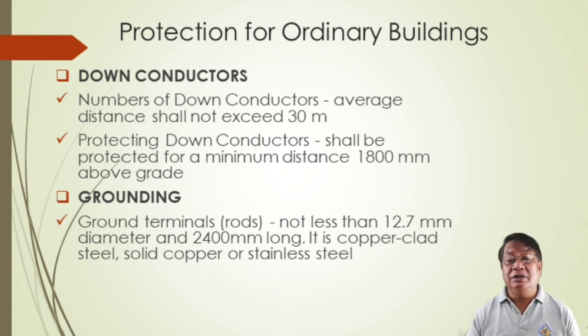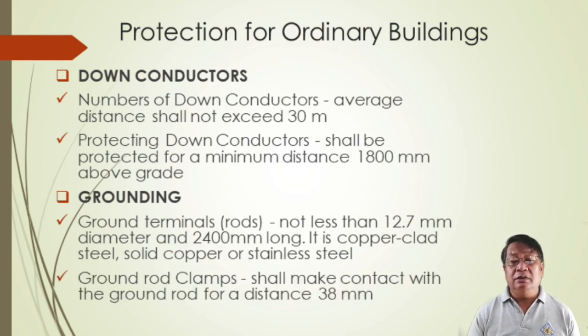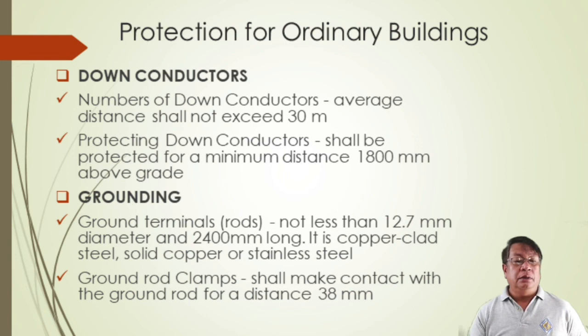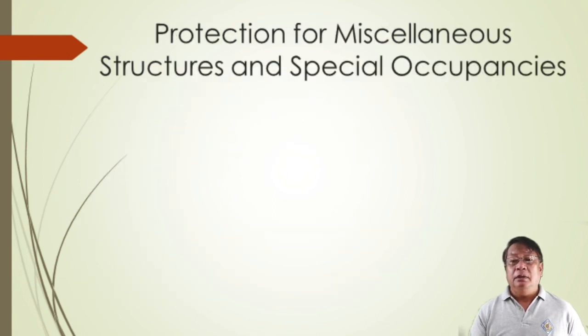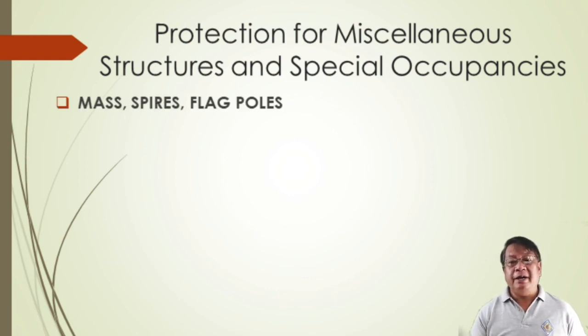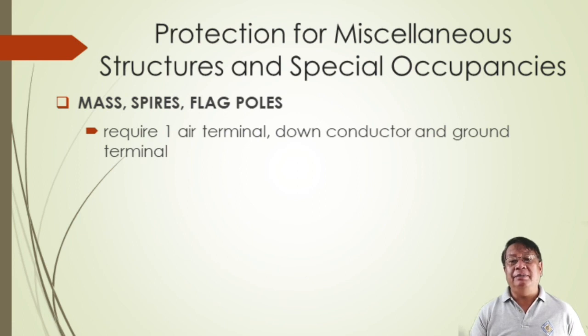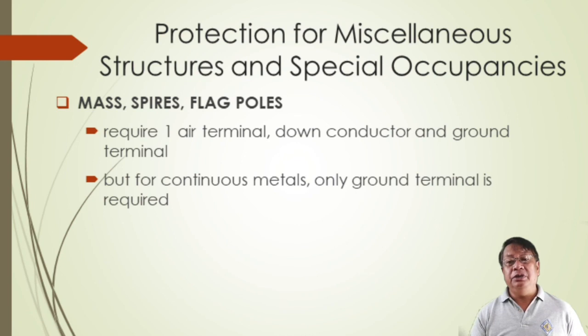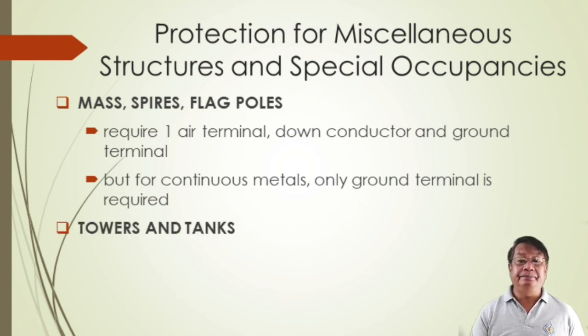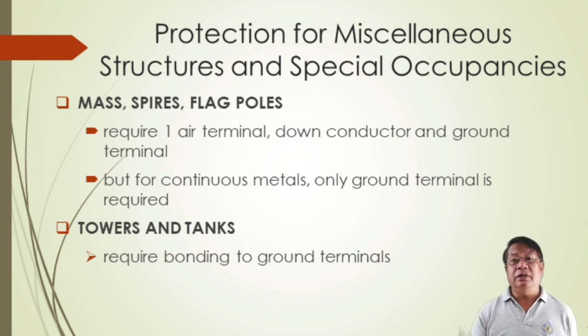For grounding terminals using rods: not less than 12.7 mm diameter and 2.4 meters long, of copper-clad steel, solid copper, or stainless steel. Ground rod clamps shall make contact with the ground rod for a distance of 38 mm. For protection for miscellaneous structures and special occupancies such as masts, spires, and flagpoles, one air terminal, down conductor, and ground terminal are required. For continuous metal structures, only the ground terminal is required. Towers and tanks require bonding to ground terminals.